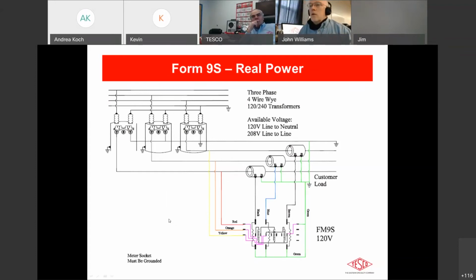The one thing that I know about the applications here is, I was at a meter school once, and they talked about the fact that maybe with 9S meters, when you're putting in new installations, you might want to take a look at that, because as far as the installation costs are concerned, versus say a 320 class 16S self-contained meter, the latter might make more sense depending on the actual application and the currents that are going to be pulled into that load, right? So if you have a 320 class 16S meter, then you don't have to worry about your CT cabinets and all that extra wiring and test switches and so forth. But you can get the same accuracy out of a 16S so long as the load stays within the 320 specification for the meter.